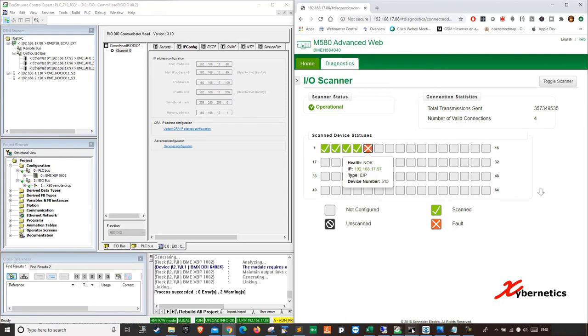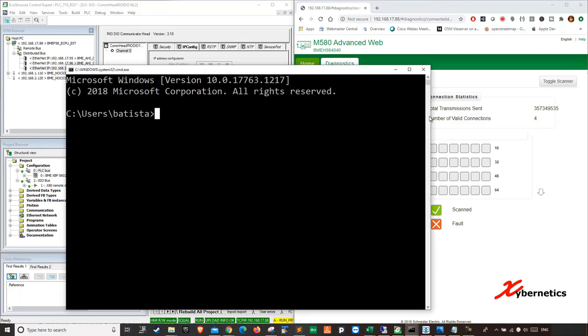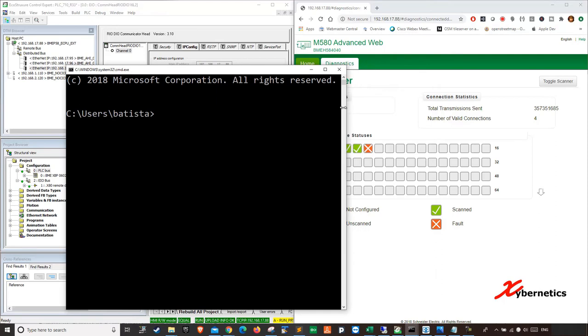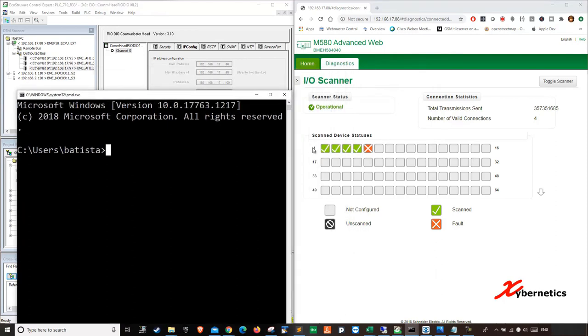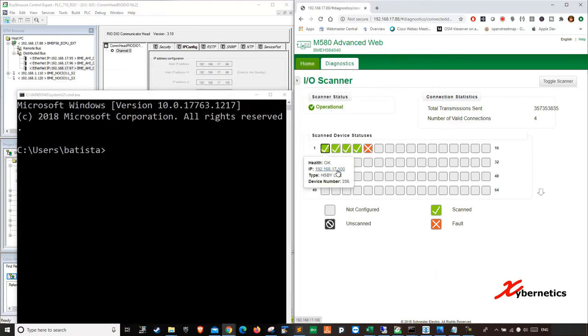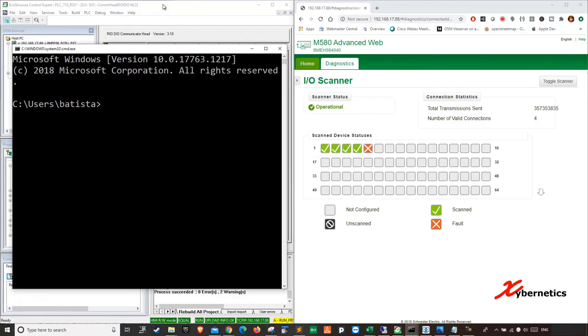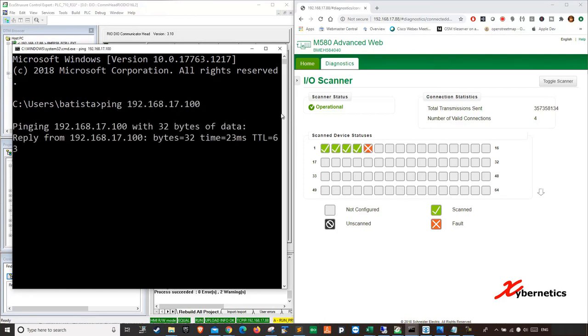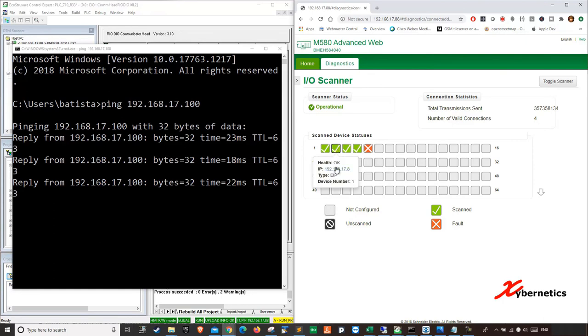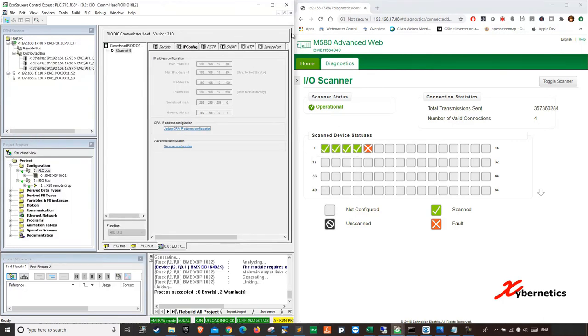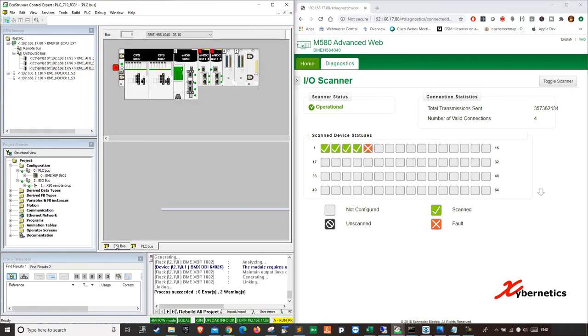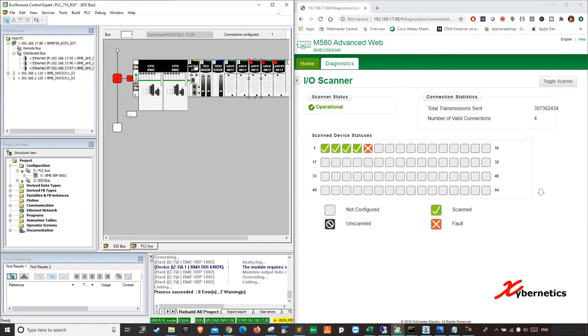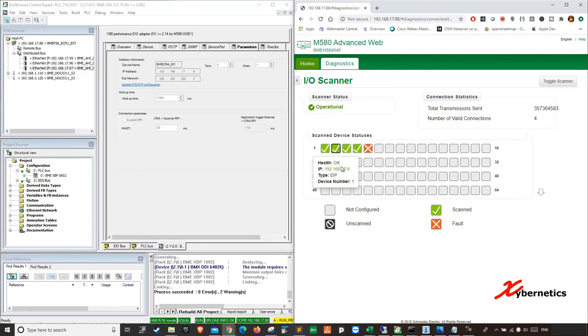Let me show you a demonstration what I mean by that. Open your command prompt. I'm going to try pinging the CPU, 17.100. Naturally, that will work because or else you will not be able to connect to it. So ping, let's do a good baseline here, 100. It talks. So this is your CRA's IP address, 17.08. How do you determine that? You go in here, double click your EIO bus, which brings you this one here, double click the CRA, and it will show you 17.08. That's how you know that this is a CRA.